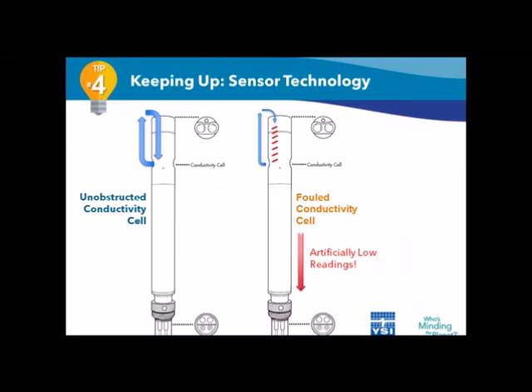So conductivity sensors are designed with drive electrodes that send current through the water towards a receiving electrode, and the amount of signal loss between those two allows us to calculate more or less the conductance of the water. And when this pathway is obstructed by some sort of fouling, then there's an artificial drop in conductivity readings, which directly impacts the quality of the data you're going to see over the course of the monitoring period.